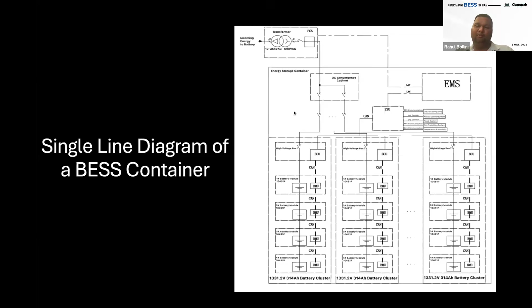Also, someone was asking about how to make components for BESS. One must understand that all the components inside BESS, although they look like normal components, are communication-enabled. For example, the cooling system is communication enabled. The fire protection system, although it looks typical, most of the time people use Novec type, which is a perfluorohexanone, these days. Earlier, people would use heptafluoropropane. In this kind of system, I think we use about 70 liters of fire protection tank. So all these are enabled by communication, and you should have that option in your component, as well as the company should have access to synchronize that. Only then can you be a component supplier for BESS.